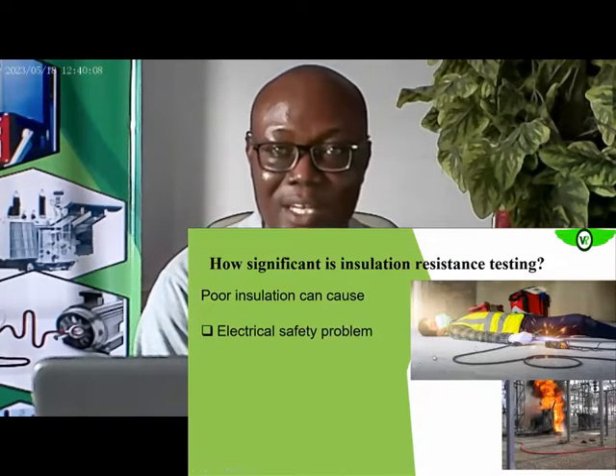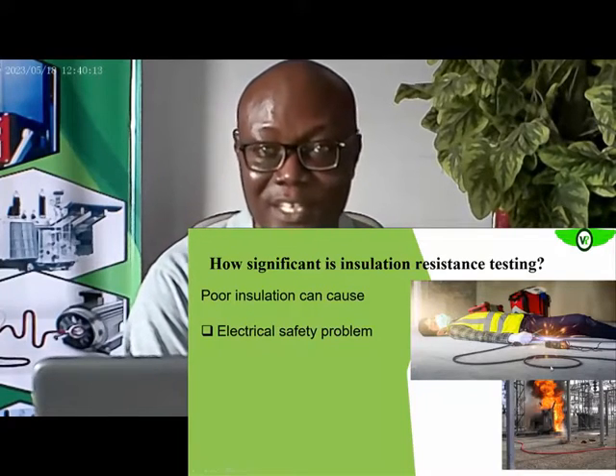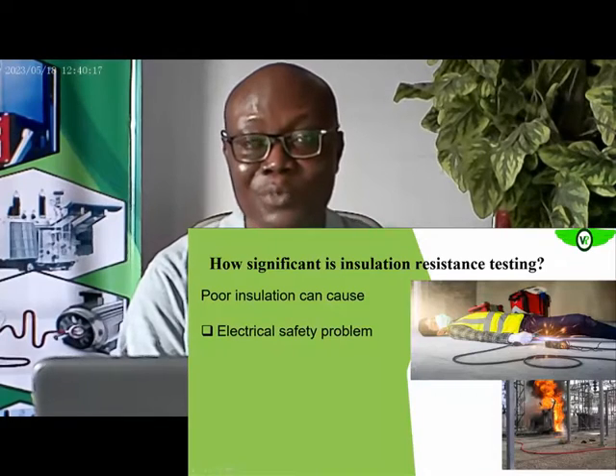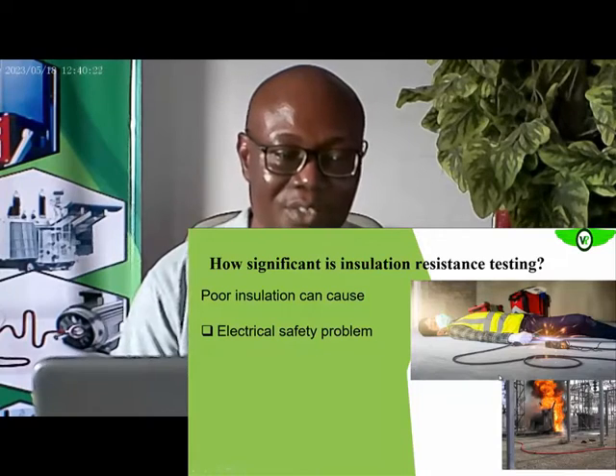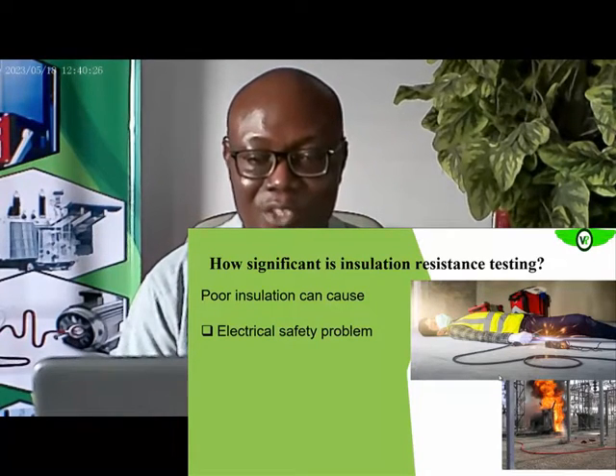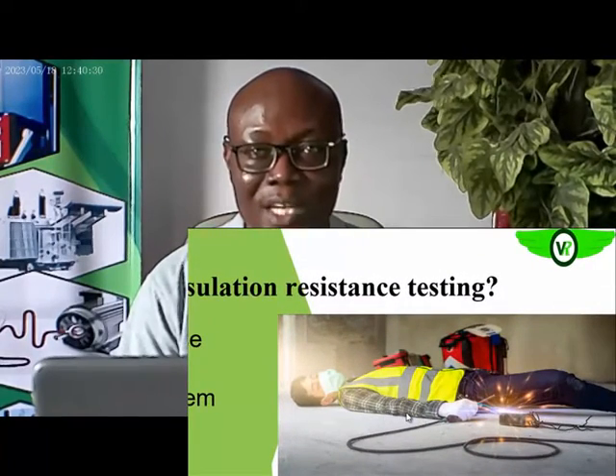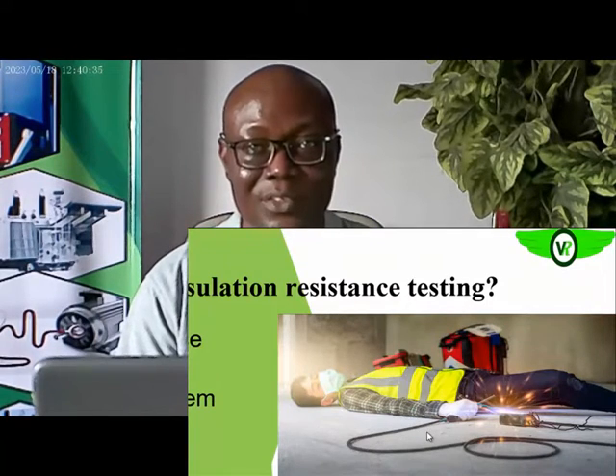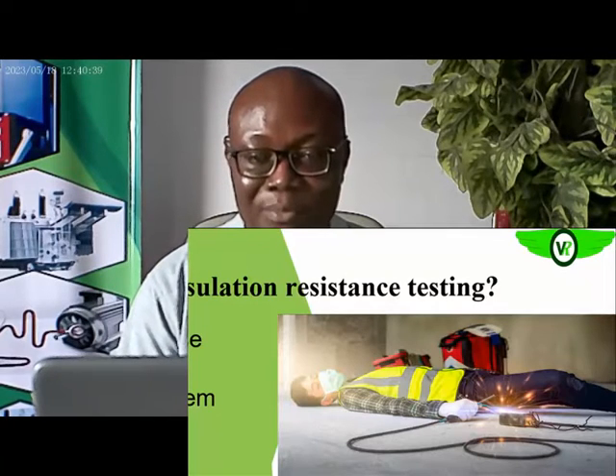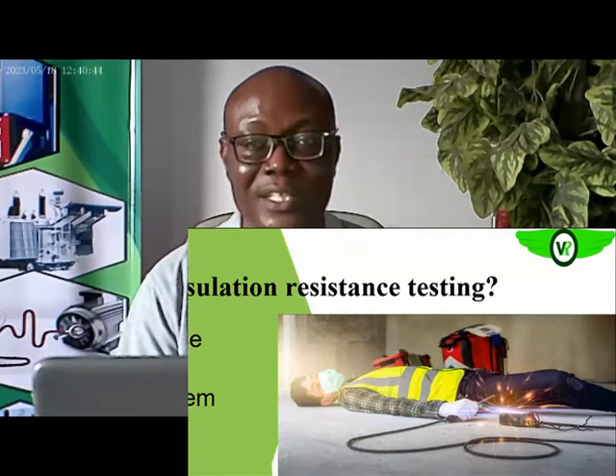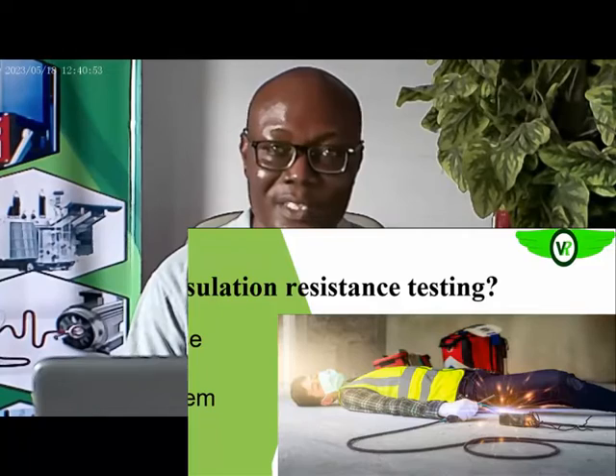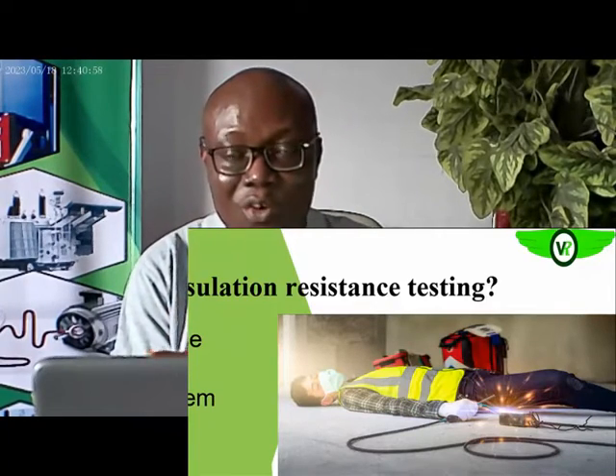So how significant is insulation resistance testing? The insulation resistance test is very important because, apart from helping you ascertain the reliability of the equipment, that the equipment will function as required without failing, it also helps to improve the safety of your electrical installation. Poor insulation can cause safety issues because it can cause interaction between live parts and ground, where you do not expect anything to be live. Once that happens, anybody accidentally touching the frame of the equipment, thinking there is no potential at that point, can suffer a safety problem or electric shock.